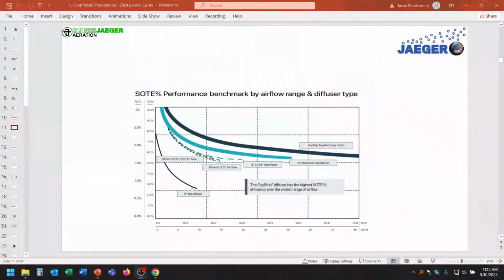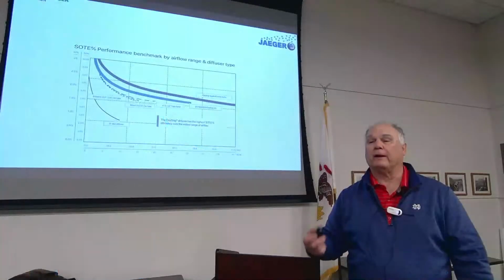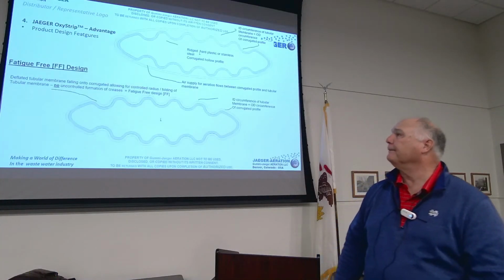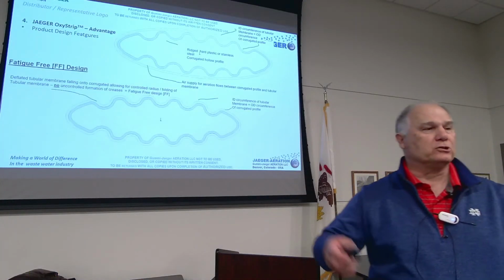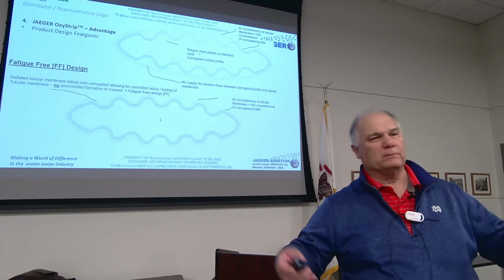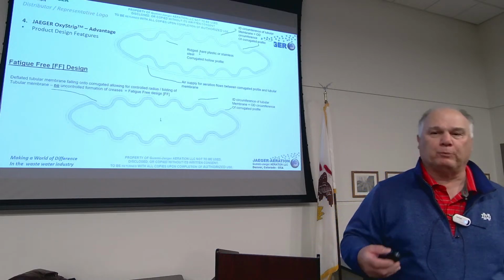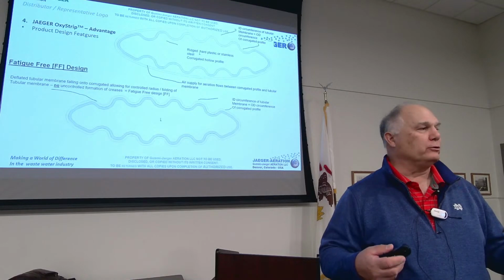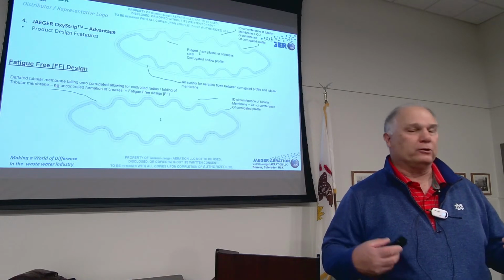Versus a strip diffuser, which is up to the top. Therefore, we use lower horsepower and fewer kilowatt hours for the same oxygen requirement that we have in the basin. Therefore, we have lower power costs.